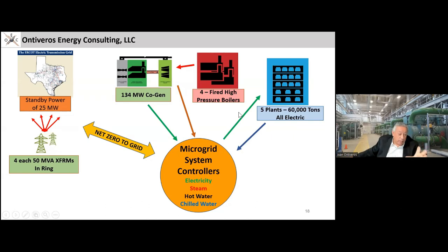Then all the electricity we produced went to chill water plants, 5 plants, 60,000 tons, all electric. And also, we use the cooling system to do inlet air cooling. In Austin, it's very hot. So in the summertime, you can get a very serious derate on a combustion turbine. A 45 megawatt turbine would only maybe give you 36 megawatts if it's 100 degrees outside. So if you can cool it to 58 degrees, you can get the full 45 megawatts. So you have a penalty in terms of cooling energy needed to cool it, but it's almost a 5-to-1 gain in efficiency. So it's a very quick payback.